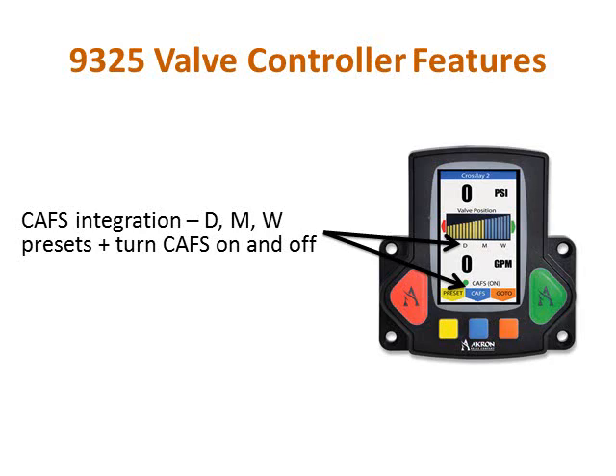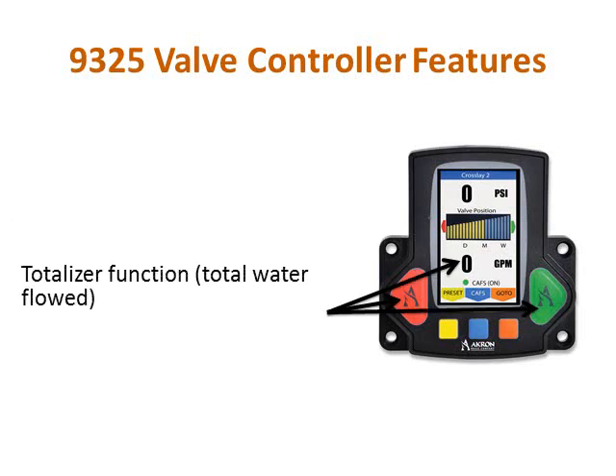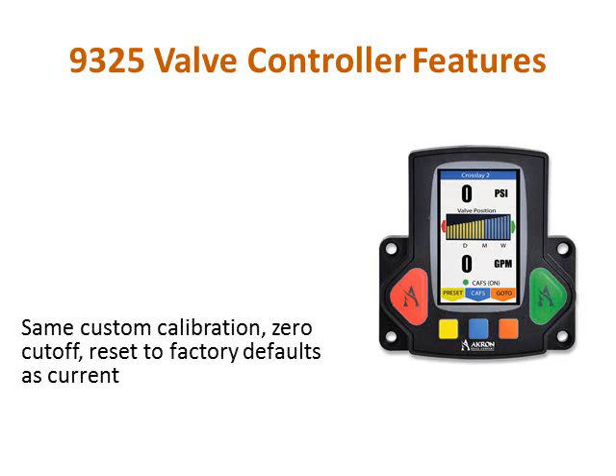With the introduction of the Navigator Pro, it is now possible to directly control a CAF system from the same display as the valve. The CAFs can be turned on and off using the blue button on the display. When CAFs is enabled, the presets display as D, M, and W, and can be set to correlate to the desired dry, medium, and wet foam. In addition, when used with the flow sensor, the Navigator Pro keeps track of the total water that has flowed through the valve since last power-up. The total water can be shown by holding both the red and green buttons at the same time. Finally, the 9325 has the same custom calibration, zero cutoff, and factory default options as previous controller versions.